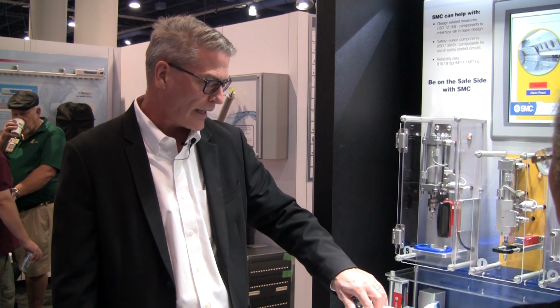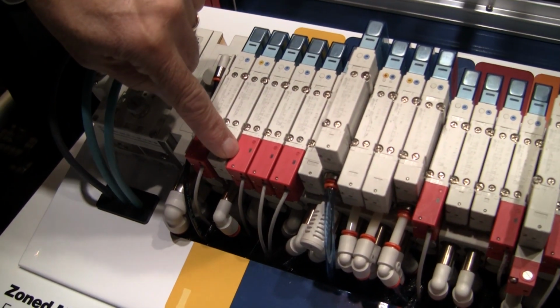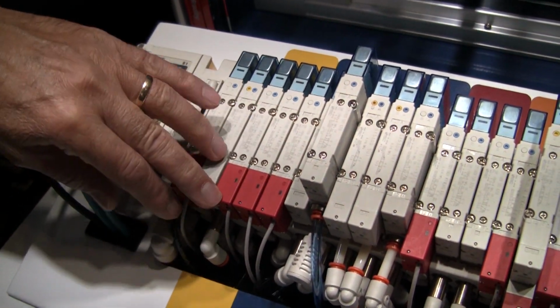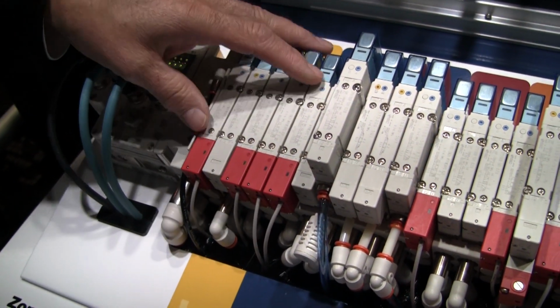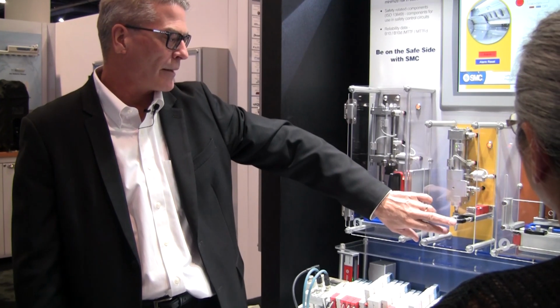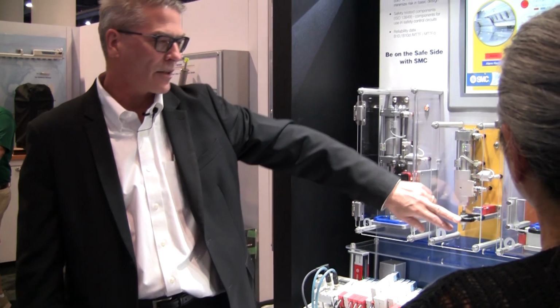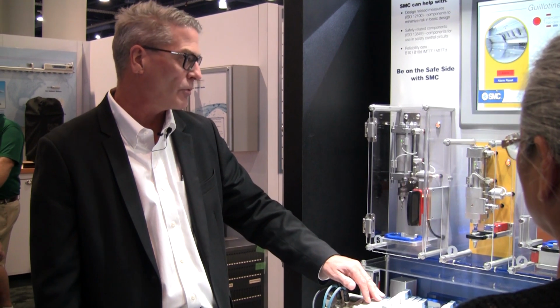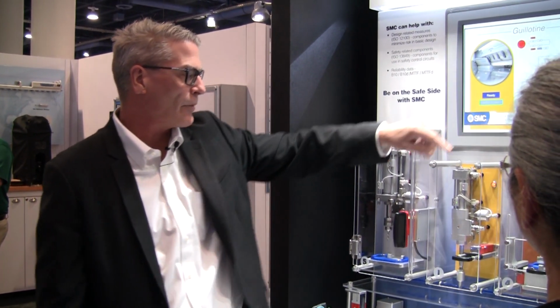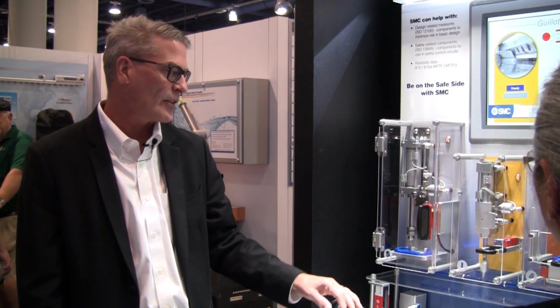And so then we also have feedback from each of these valves confirming stop, and we have feedback from the pilot-operated check valve. But the beauty of a system like this is that the rest of the machine has been able to continue operating, and recovery from the safe stop is very painless. It goes right back to work once we've adjusted the problem.